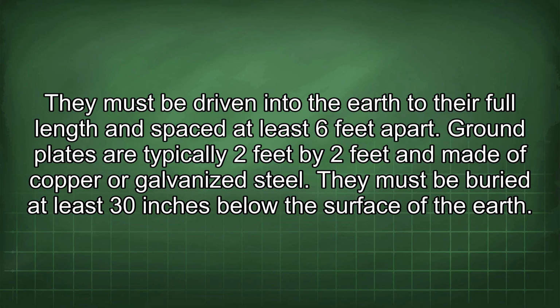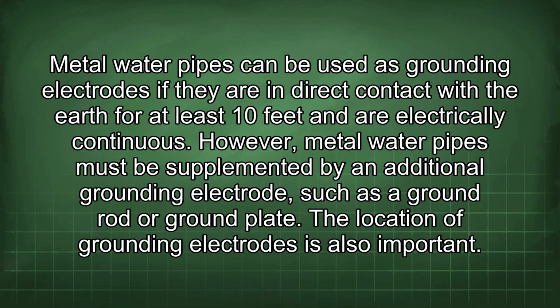Ground plates are typically 2 feet by 2 feet and made of copper or galvanized steel. They must be buried at least 30 inches below the surface of the earth. Metal water pipes can be used as grounding electrodes if they are in direct contact with the earth for at least 10 feet and are electrically continuous. However, metal water pipes must be supplemented by an additional grounding electrode, such as a ground rod or ground plate.